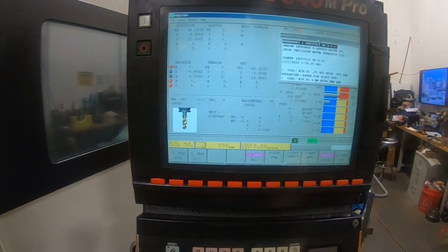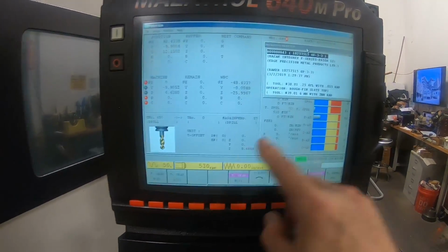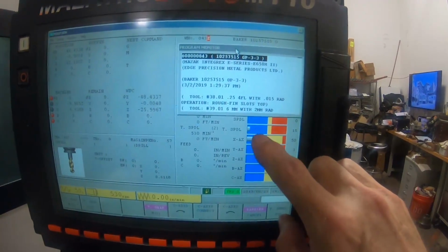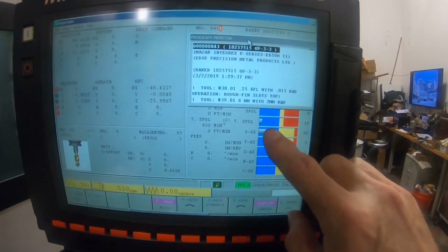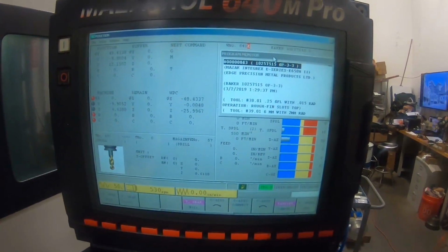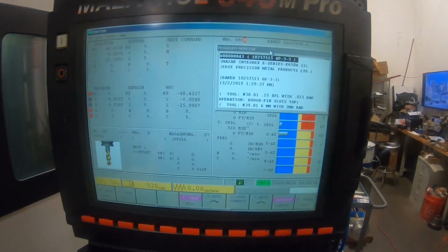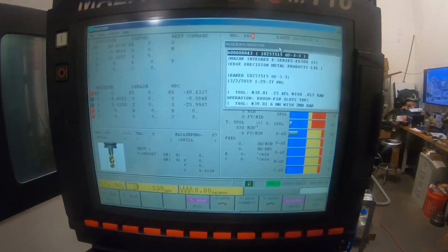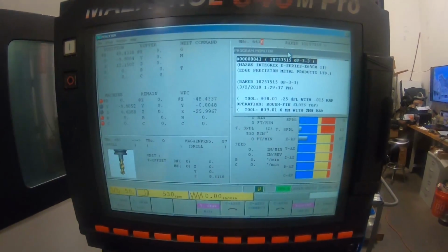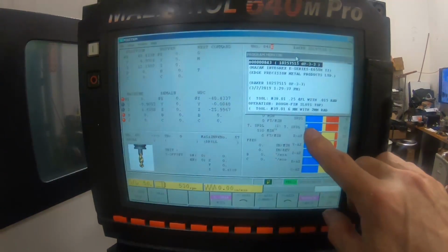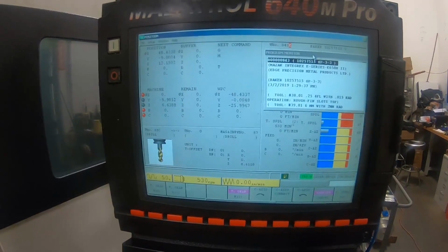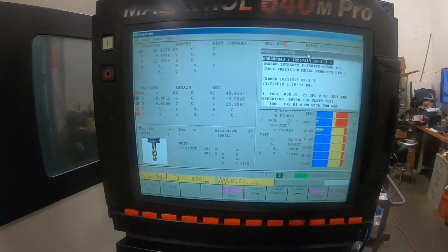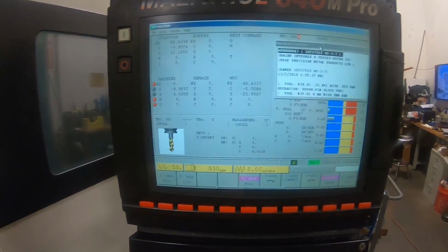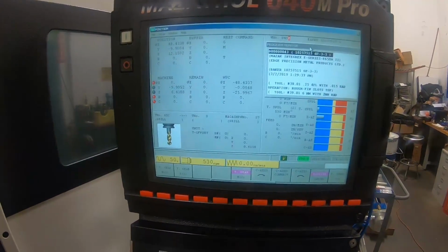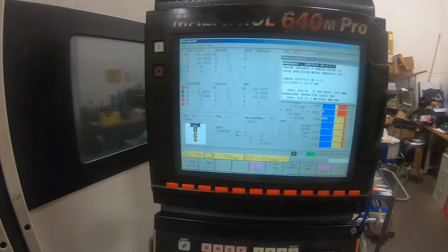If I back the speed back down to something normal for it to stay in the Y configuration — the Y configuration of windings is for lower speed because it has lower voltage on the motor but more windings in each leg, since the windings are in series — then it shifts to the delta windings, which puts full voltage on each winding, so it can go up to higher speeds with more torque, apparently, as I understand it.